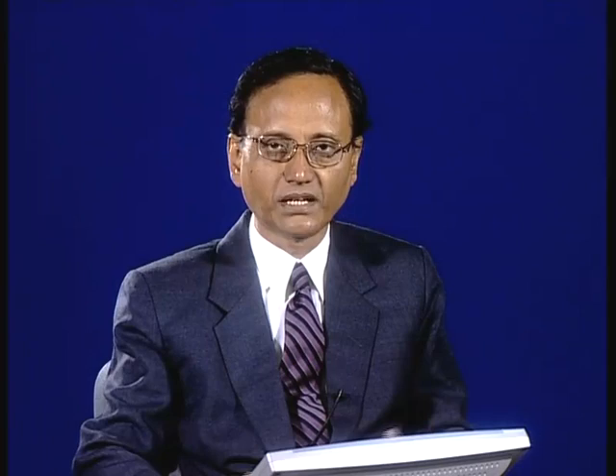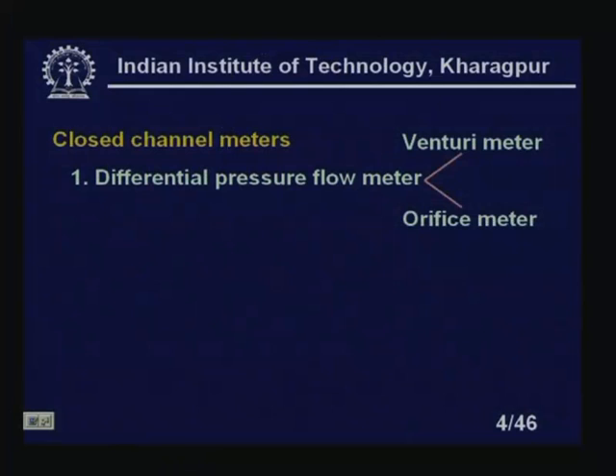Looking at closed channel meters — in a closed pipe, we mostly use differential pressure flow meters such as venturi meters and orifice meters. Variable area flow meters — the rotameter — are also used in closed channels. In open channel meters, such as for irrigation purposes, we need to measure the velocity of fluid to calculate total liquid quantity. For open channel, we have two types: weirs — V-notch and rectangular — and the pitot tube.